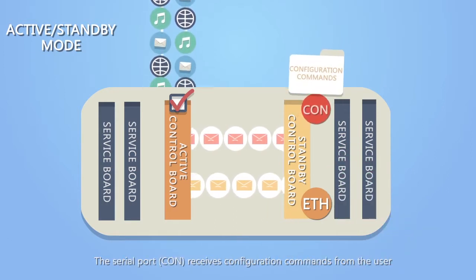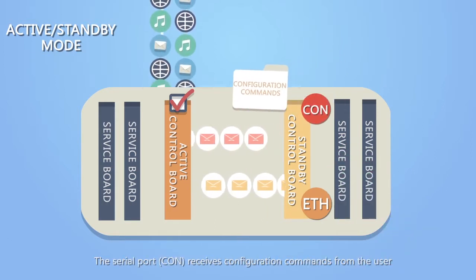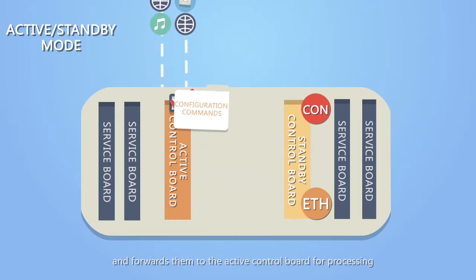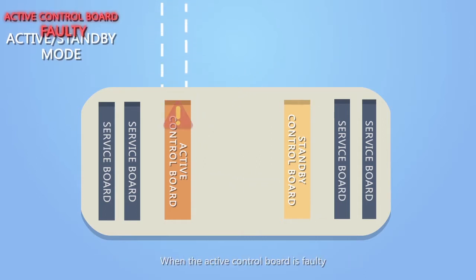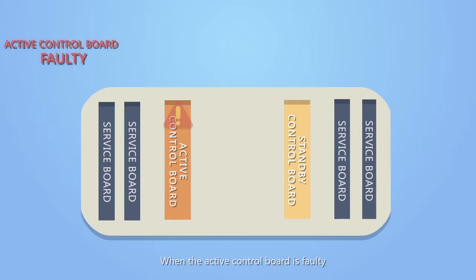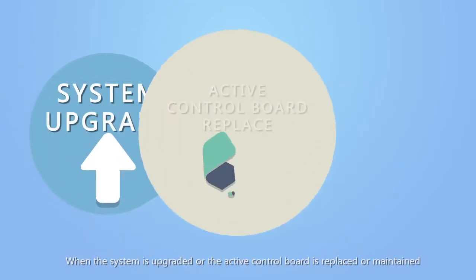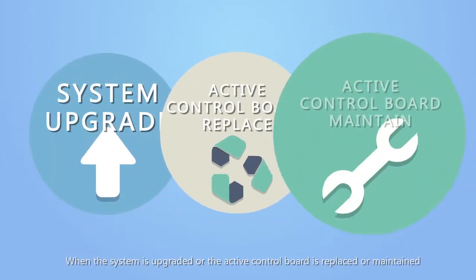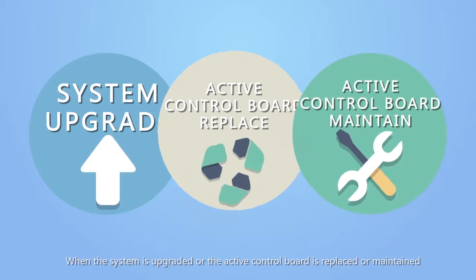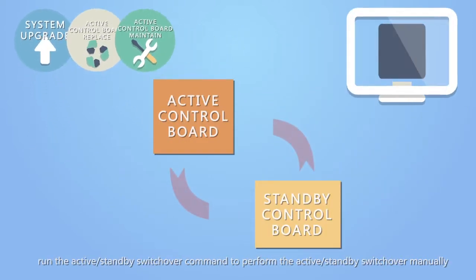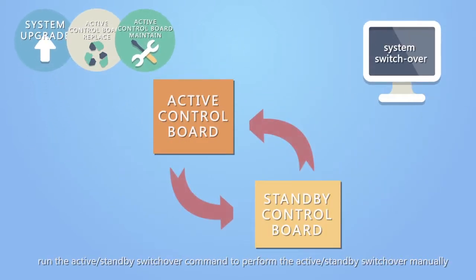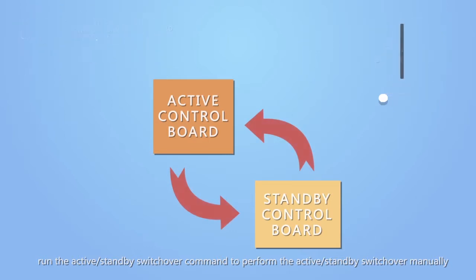The serial port, CON, receives configuration commands from the user and forwards them to the active control board for processing. When the active control board is faulty, the system automatically performs the active standby switchover. When the system is upgraded or the active control board is replaced or maintained, run the active standby switchover command to perform the active standby switchover manually.